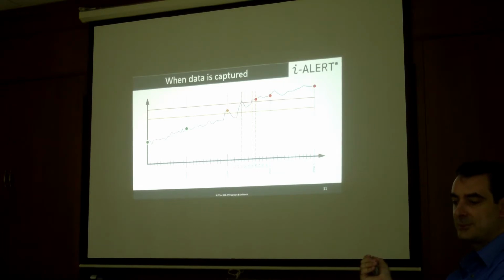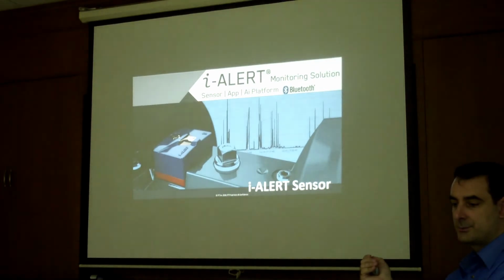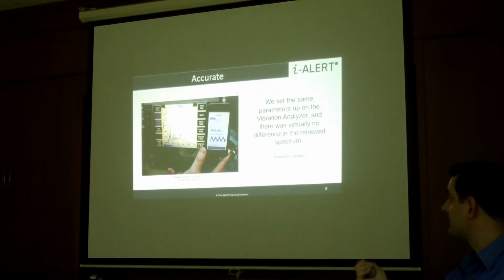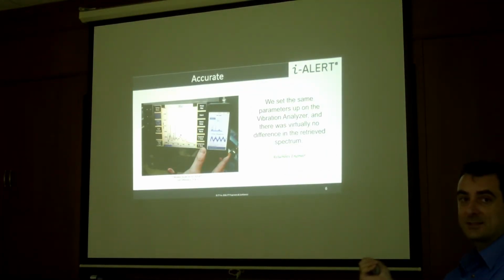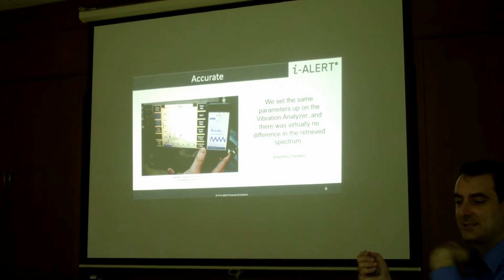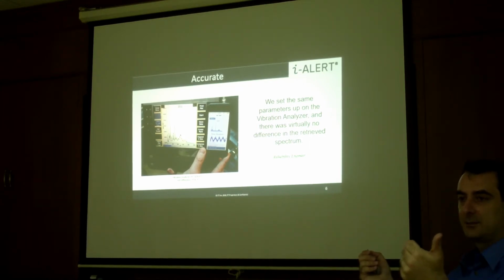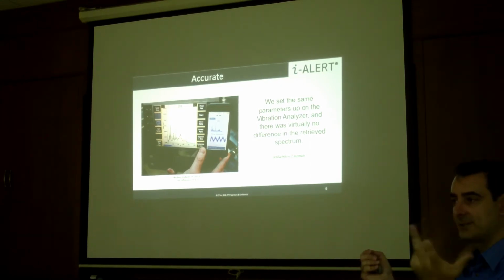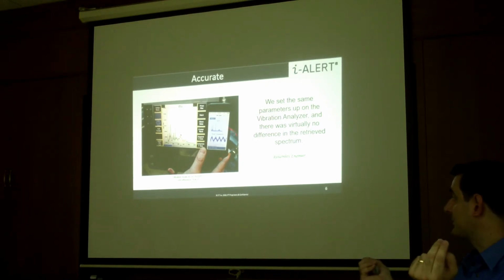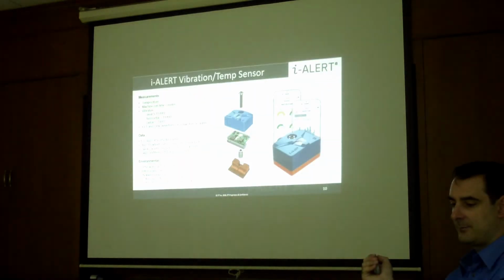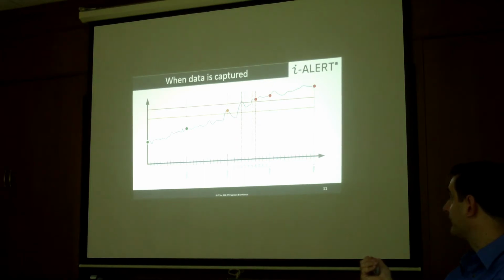That is also where we capture the time waveform or the vibration spectrum, which is this. And this will help the customer find out why the vibration crossed the point. So we often can diagnose here vane pass frequency, which will tell us, and then the shape of the graph will tell us if it's deadhead, run out, or suction. We can tell the three different by this graph. And we capture that at this point.